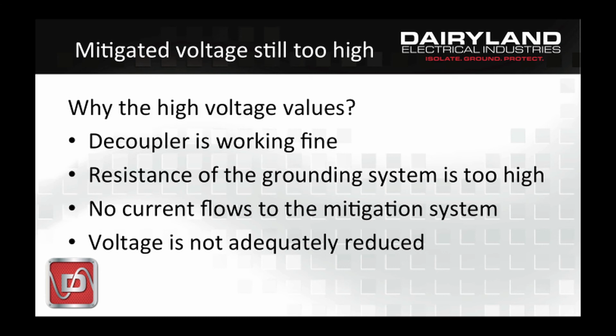So why would you have high voltage values on a pipeline? Well, we can assure you in almost every situation the decoupler is working just fine. And there's ways we can prove that, and we'll have a last slide here to talk about that. However, the basic problem is the resistance of the grounding system is too high. It's not a very effective ground, so no current, or not enough current, flows to the grounding system, and by this we mean AC current flows to the grounding system. So the voltage is not collapsed on this system. And if the voltage is not collapsed, one would say, well, the mitigation system isn't working.